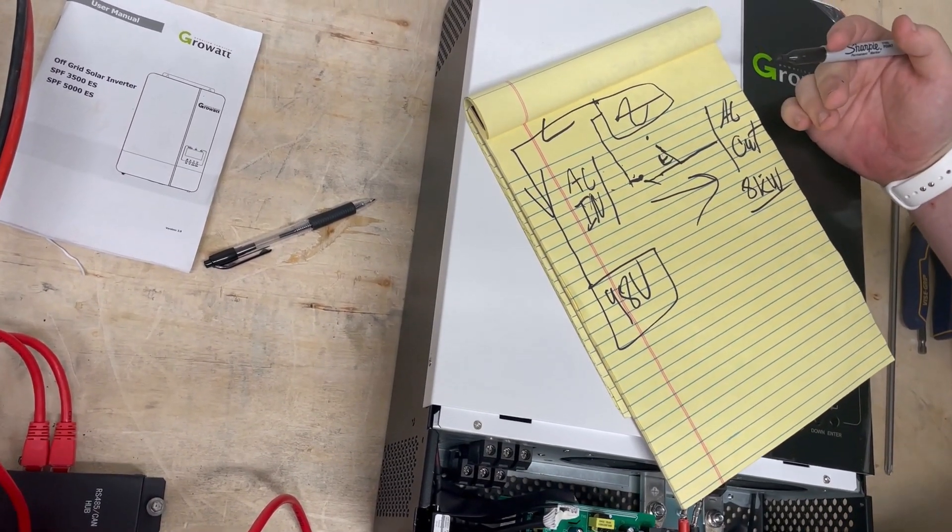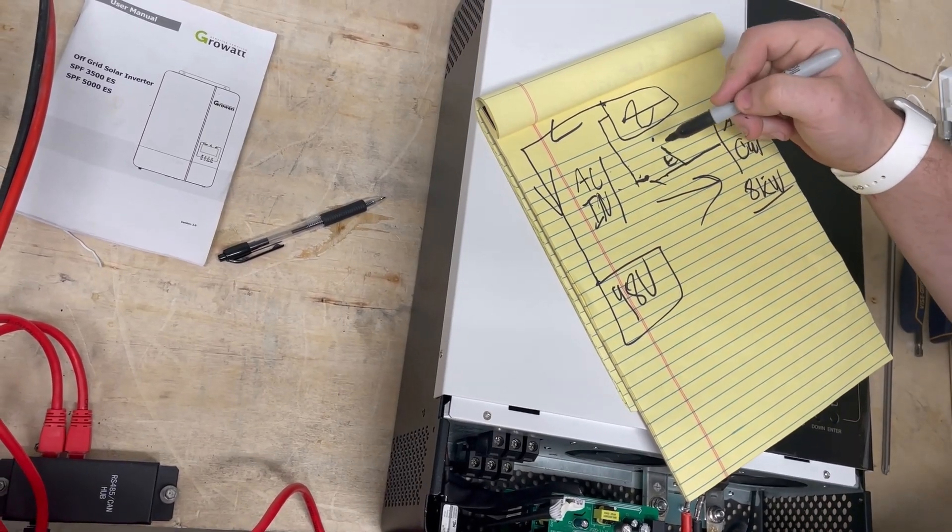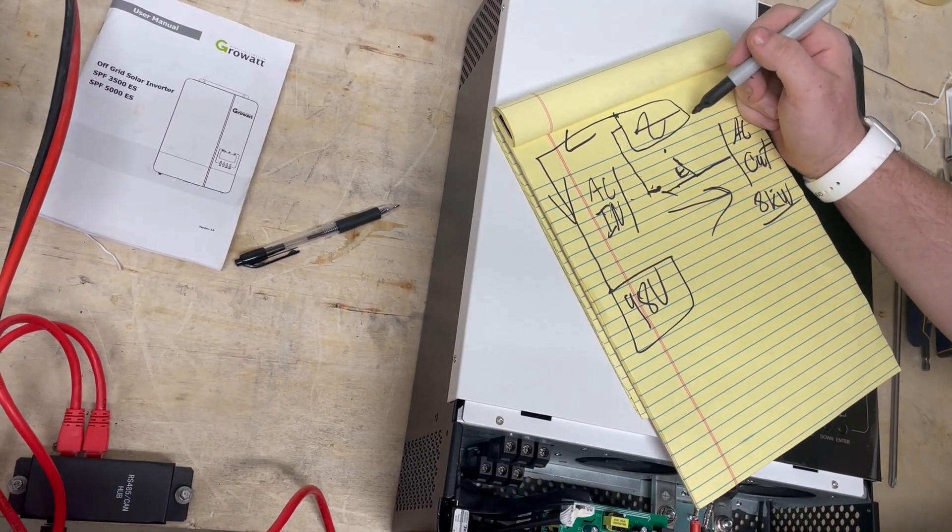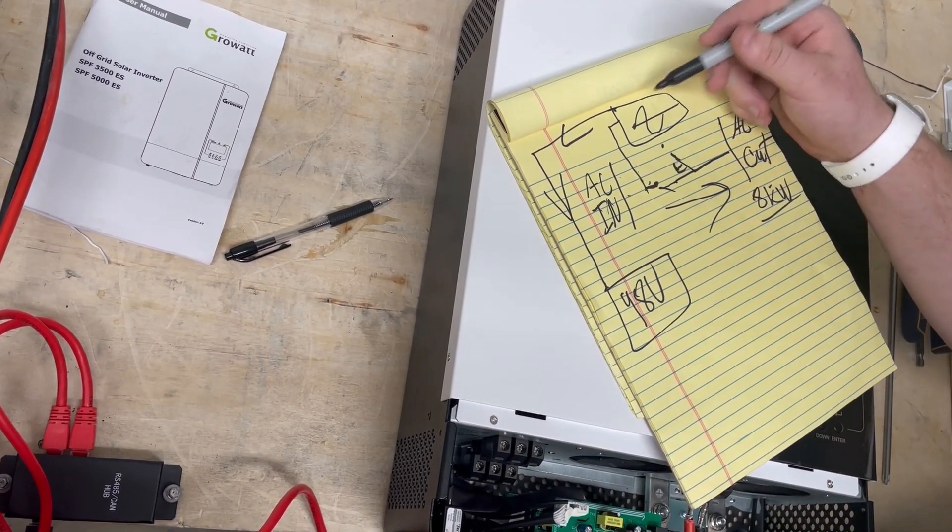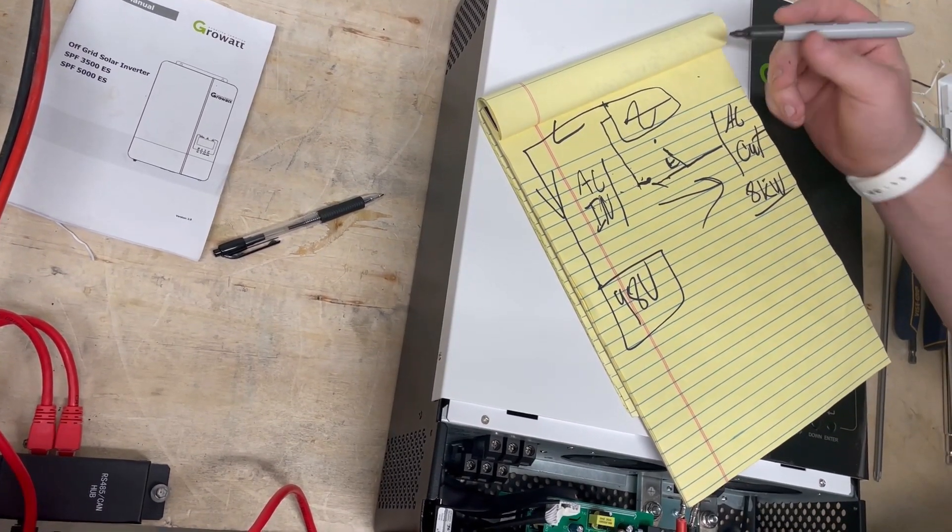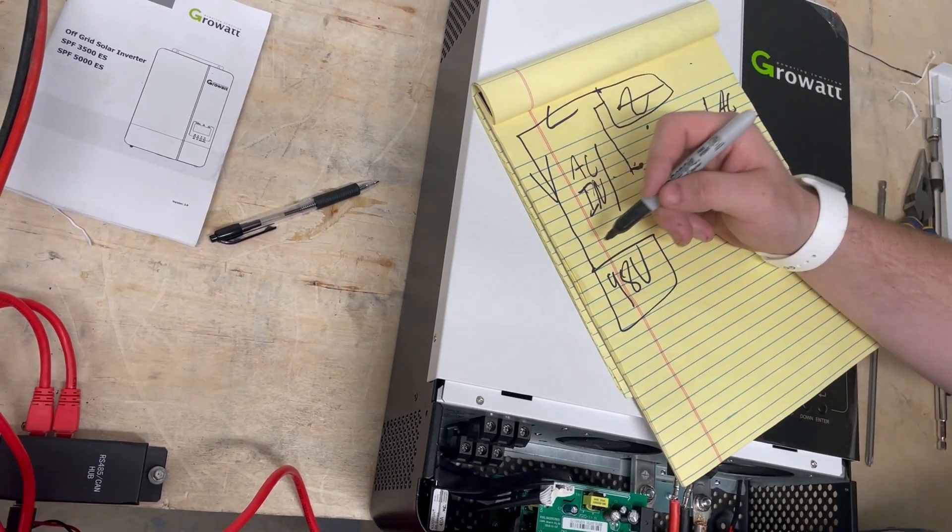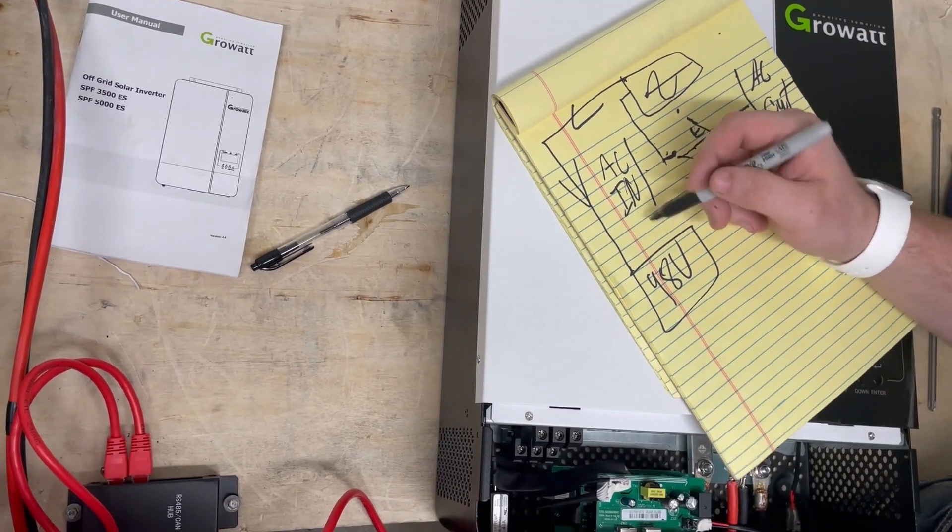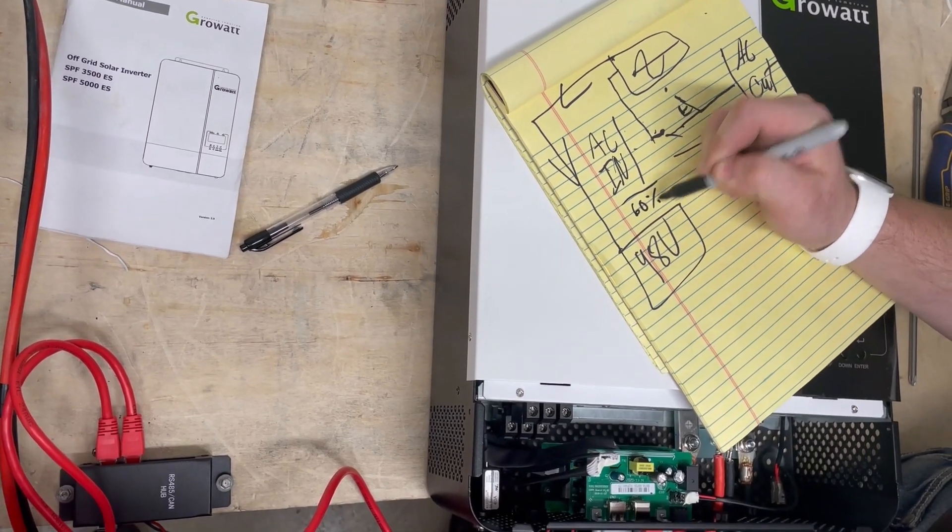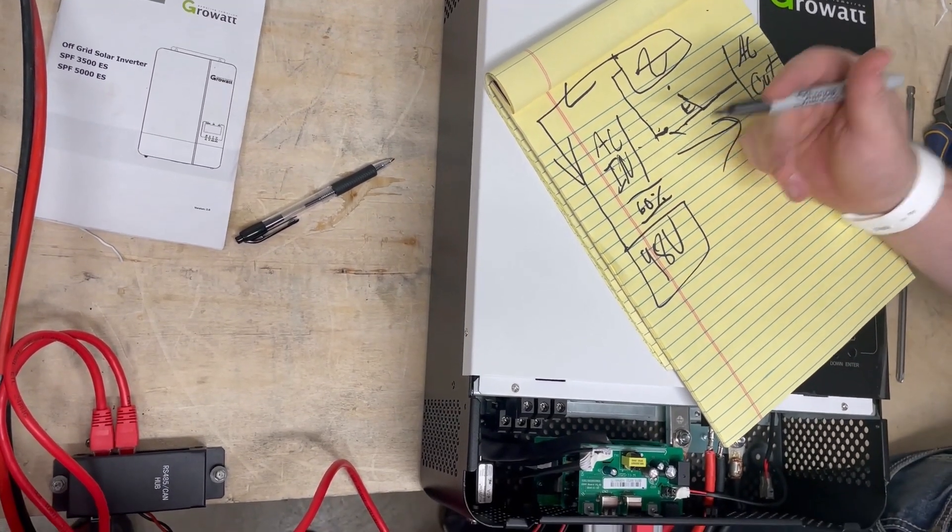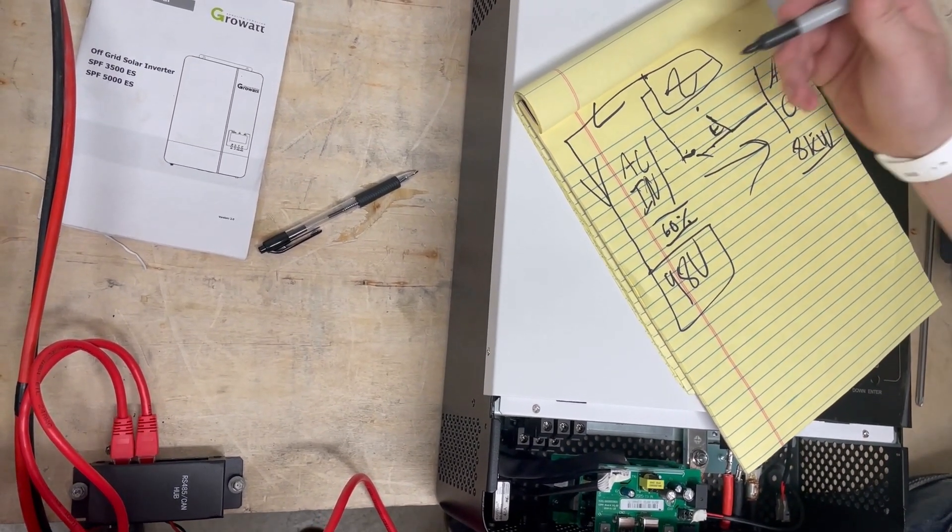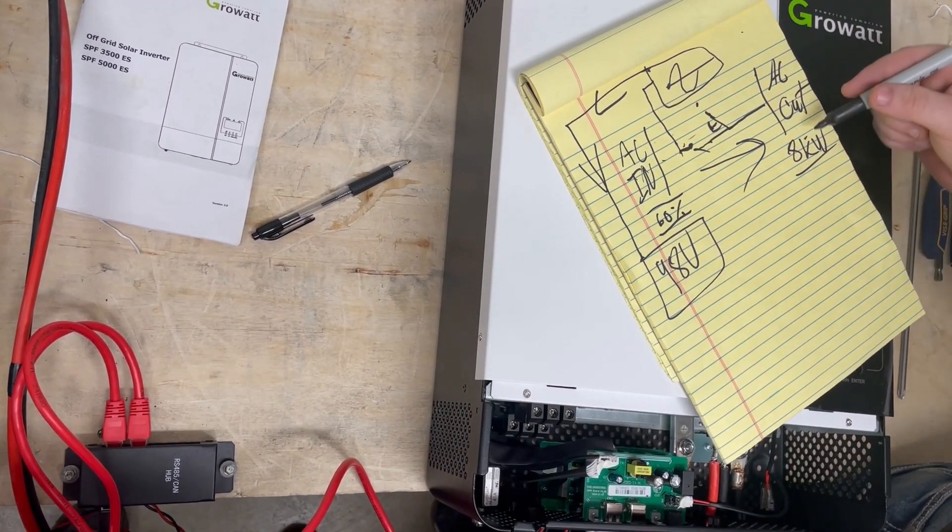The next thing that will happen is the inverter will seek to load the AC input and try to charge the batteries. The problem is that each of these inverters can be putting in up to about 4,000 watts of power to the batteries. So if I have three of them, that's 12 kilowatts. I can potentially ramp down the power, but I'm still limited by another factor: a generator needs to be kept under 60%. This is important - 60% of nameplate rating. After 60% load, the generator power quality will collapse and that will cause damage to your inverter.